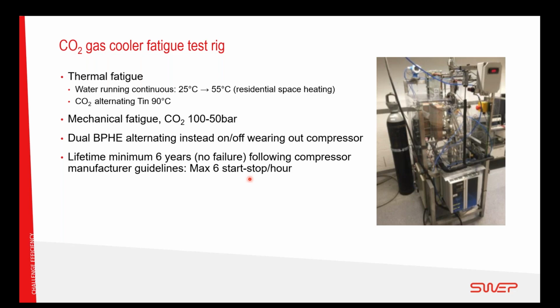And this represents, if you follow the compressor manufacturer guidelines, where we have a minimum 10 minutes between the start and stop. So that's reaching 6 starts and stops an hour. So this is minimum 6 years of lifetime for this CO2 gas cooler. It's quite a demanding application. So this is some of the products that we have done in the last years.